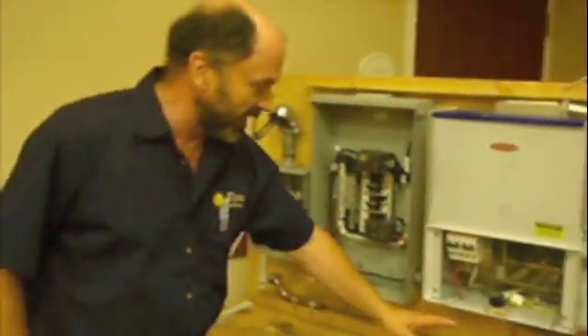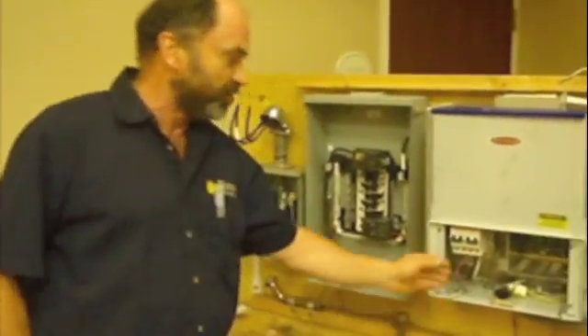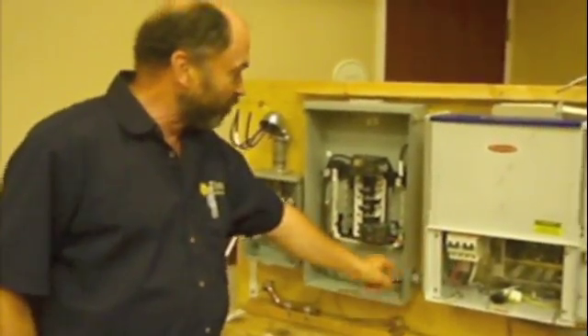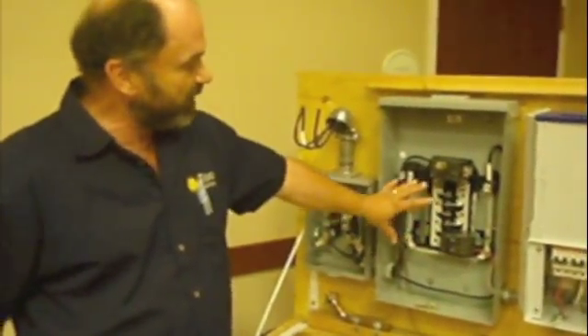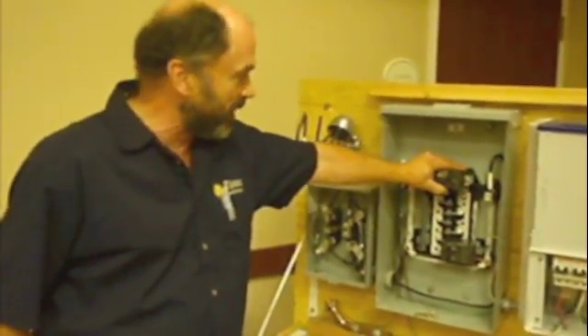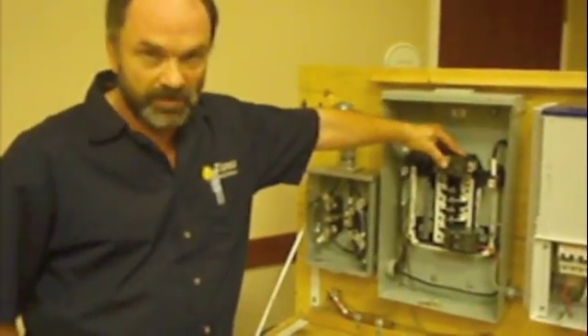We come out of this device with AC power, typically 240 volts, and feed into a back fed breaker in the panel. We are allowed to back feed into a panel that is already fed with its full capacity on the main breaker and exceed that rating by 20 percent.